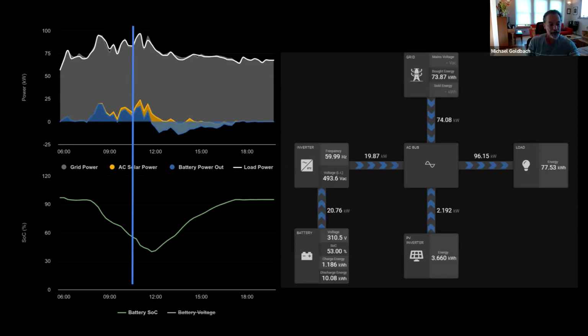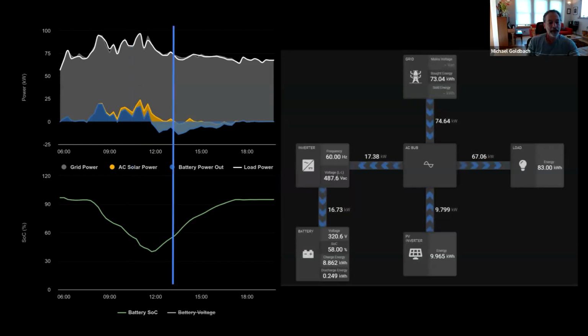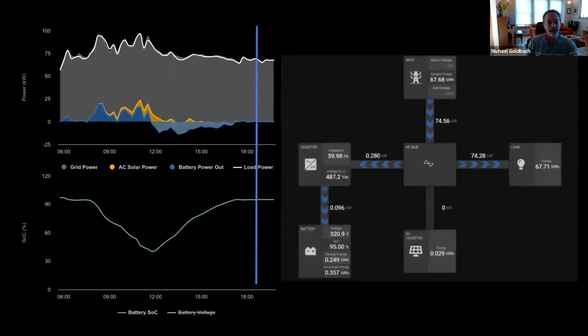So you see that the battery's been discharging, the state of charge goes down, and then later in the afternoon, you can click one. So about 1:30, the load is low enough that the controller is saying, okay, now I can start recharging the battery, still maintaining the grid below that 80 target, but now using the grid to recharge the battery, getting it back up to 95. You can see that on the green line, but also in the bottom left-hand block of the diagram that says the battery is now at 95, so it's not consuming from the grid anymore. It's just allowing the grid to meet the load. So that's just an example of a day of controls.